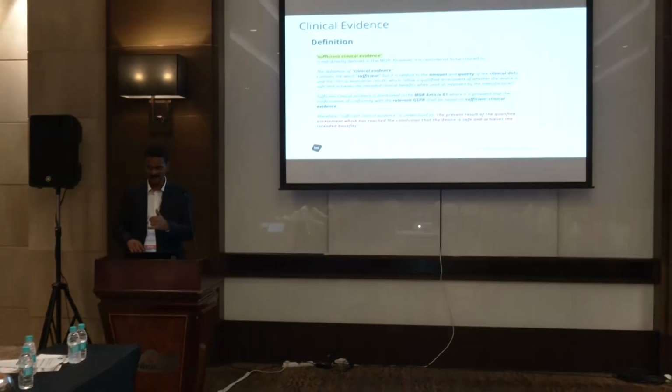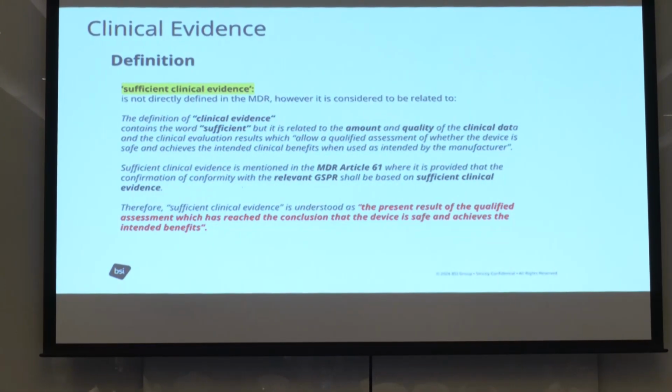Okay, I talked about clinical evidence. The MDR says there should be sufficient clinical evidence, but there is no definition given in the MDR about what is sufficient clinical evidence. But when you analyze it, it says the present result of the qualified assessment has reached the conclusion that the device is safe and achieves the intended benefit. That means the quantity and quality of the clinical data matter. That is what sufficient clinical evidence means.